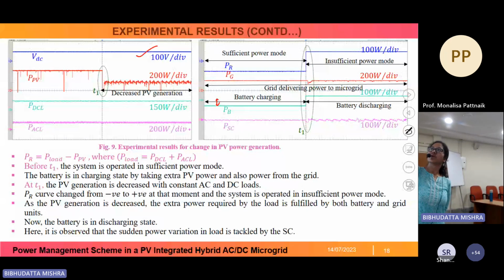Suddenly at T1 second, we reduce the PV generation. As the PV generation is reduced, the PR value increases and becomes positive. During this condition, as PV generation is reduced, the battery changes from charging state to discharging state. Previously it was in negative power, meaning charging, and now it is in positive power, meaning discharging. Throughout this condition, as grid power is positive in both cases, the system is in grid delivering power mode.